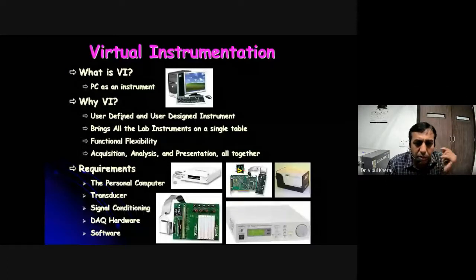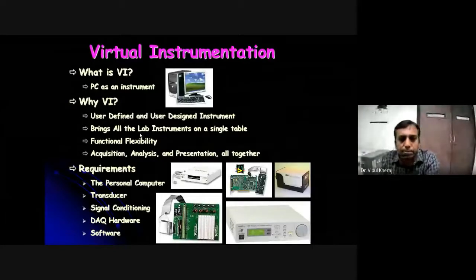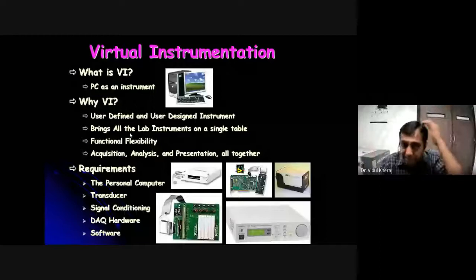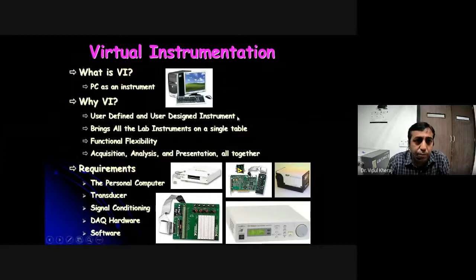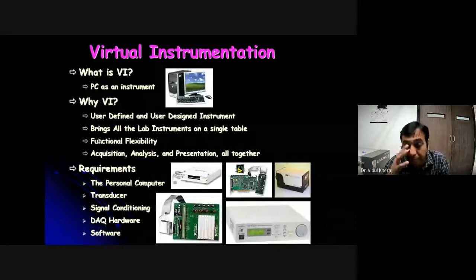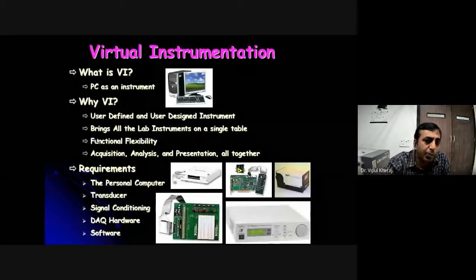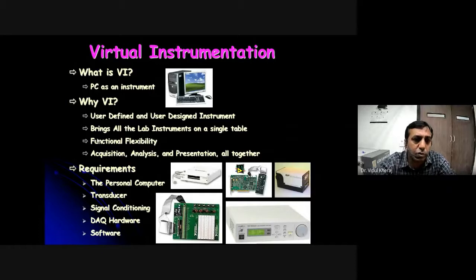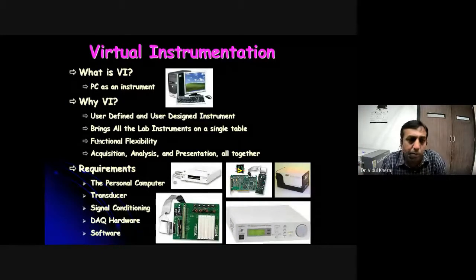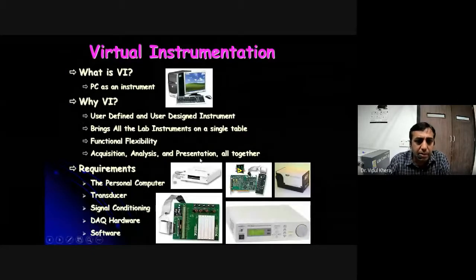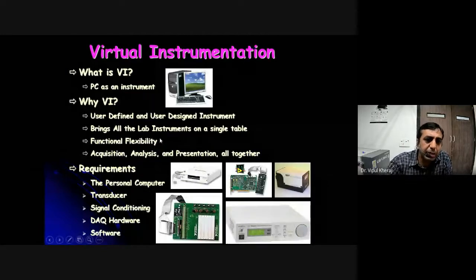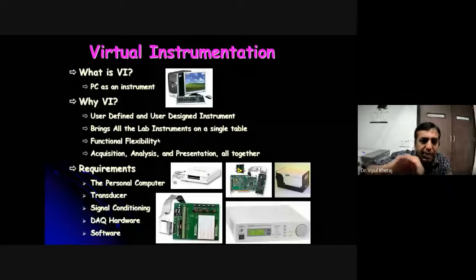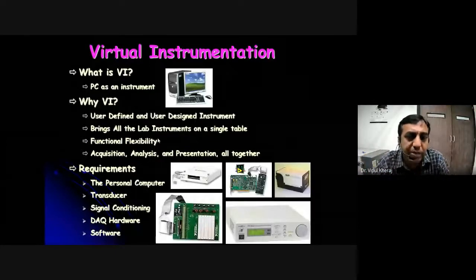You define the instruments you want in your experiment and their sequences — at what time which event takes place and what measurement will be carried out. It is a user-defined and user-designed instrument. This also brings all the lab instruments onto a single table. For my spectroscopy experiment I have a monochromator, lock-in amplifier, and detectors — and I want all of them on a single platform where I'm talking to all of them simultaneously.